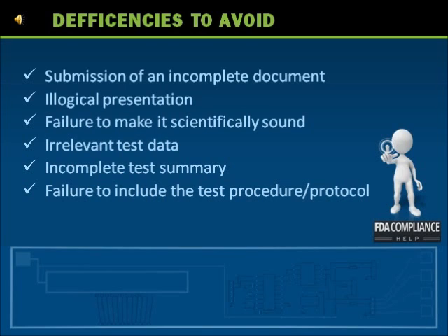To facilitate FDA review of the data, analysis, and conclusions in the application, you should be sure the submission is a logical presentation of the data, your test results and analysis is scientifically sound, the relevance of the test program to the device and intended use is easy to discern, and the summary report of the tests is complete. A description of the tests and the results obtained are essential. Reasonable and sufficient details of all test procedures and results should be included.